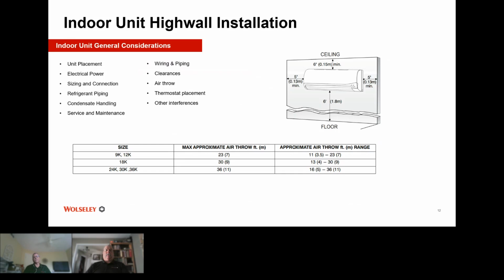Air throw: again, in front of it you've got to have enough room that you can get lots of air flowing out there and not coming back to the unit, so it's not reading the temperature of the air coming back right away. It's got to be able to go out and penetrate that room.